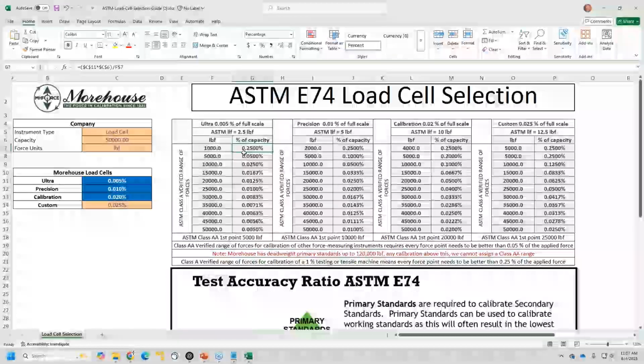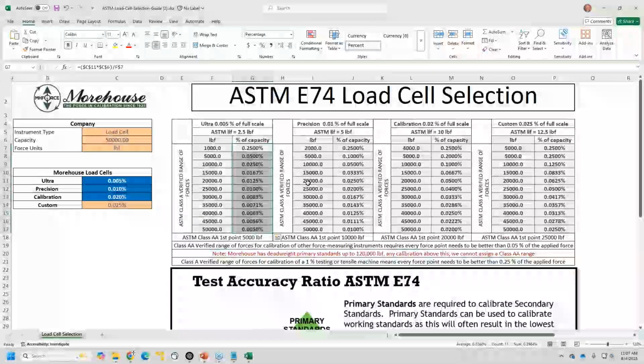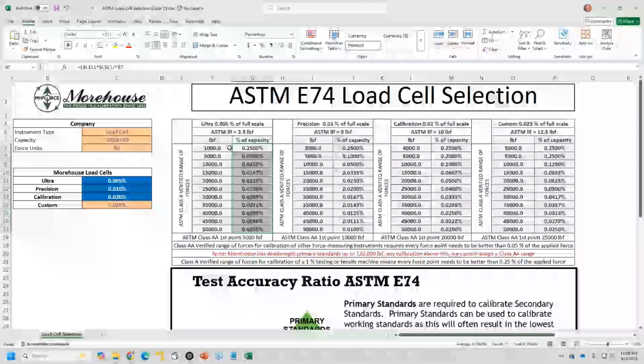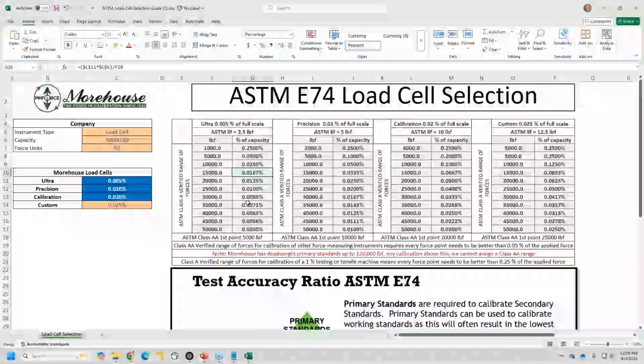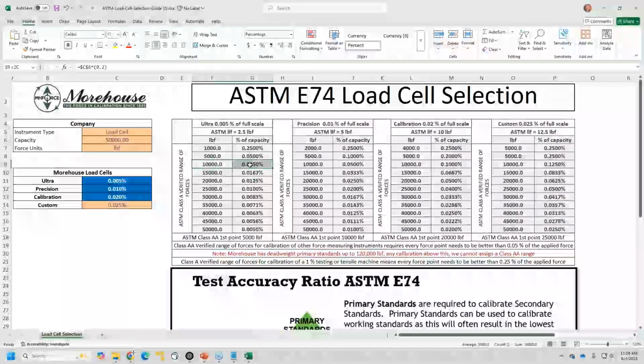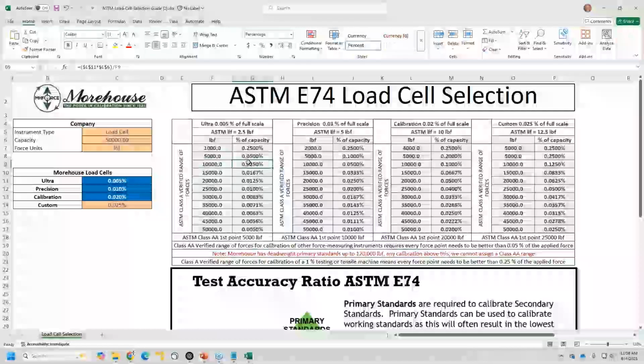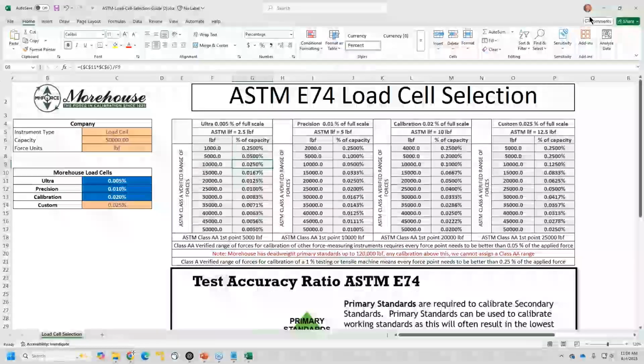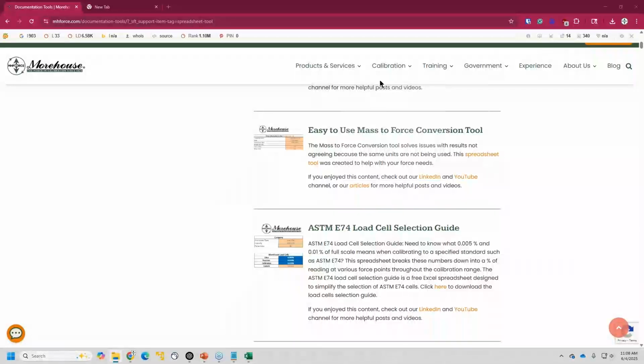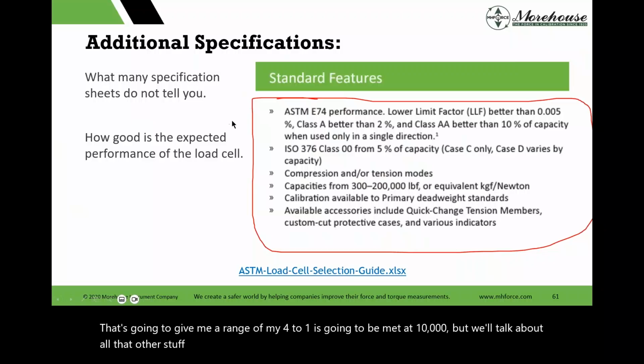And depending what I want to maintain, if I'm using test accuracy ratios, which I do not recommend, that would mean that if I wanted a 4-to-1 on a 0.1%, I may have to buy the Ultra cell, because if I'm calibrating devices to 0.1%, my 4-to-1 is going to be met at 10,000. But we'll talk about all that other stuff in a bit.